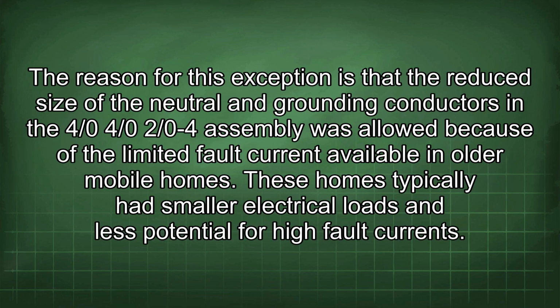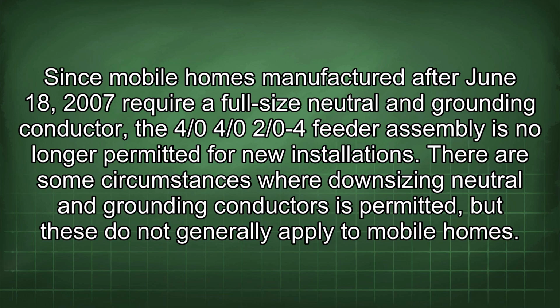The reason for this exception is that the reduced size of the neutral and grounding conductors in the 4/0-4/0-2/0-4 assembly was allowed because of the limited fault current available in older mobile homes. These homes typically had smaller electrical loads and less potential for high fault currents. Since mobile homes manufactured after June 18, 2007 require a full-size neutral and grounding conductor, the 4/0-4/0-2/0-4 feeder assembly is no longer permitted for new installations.